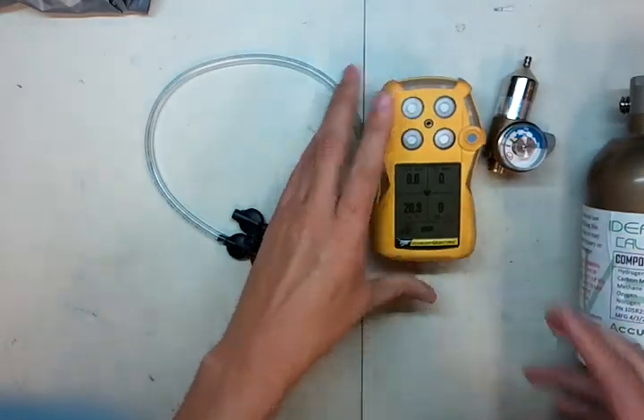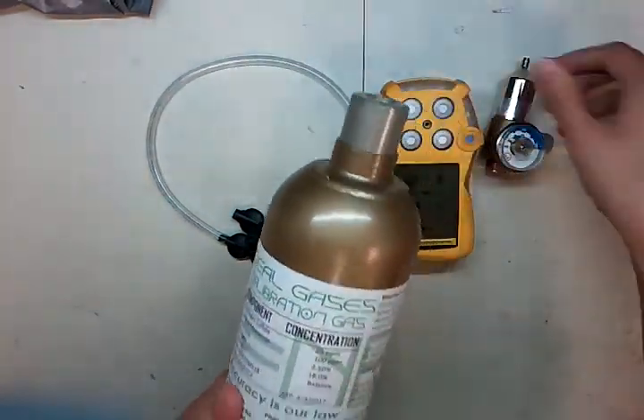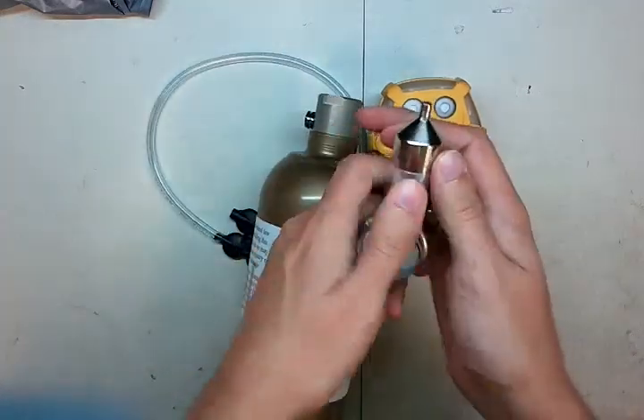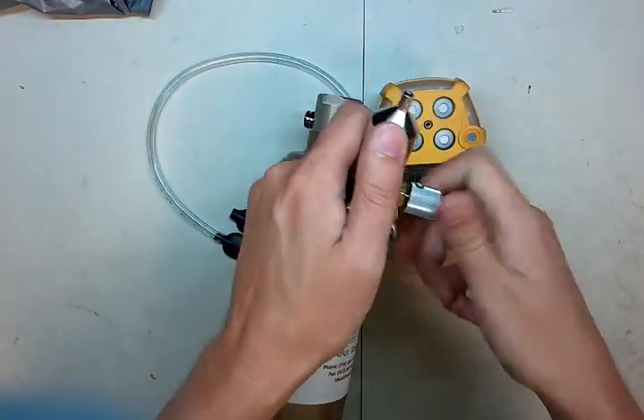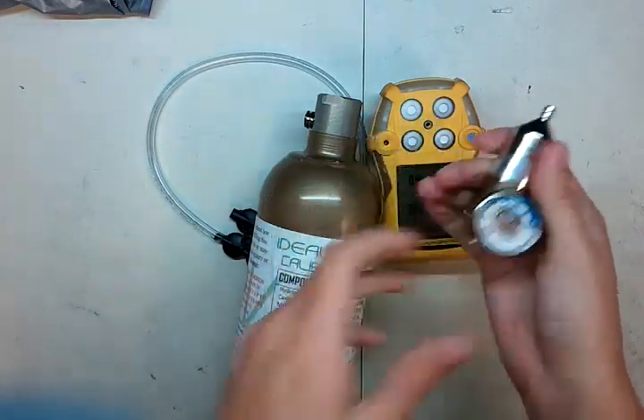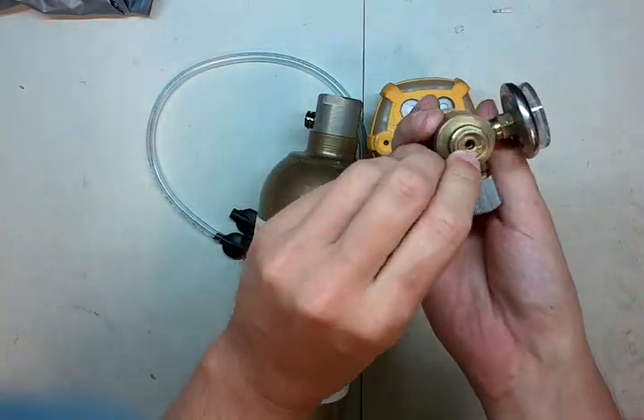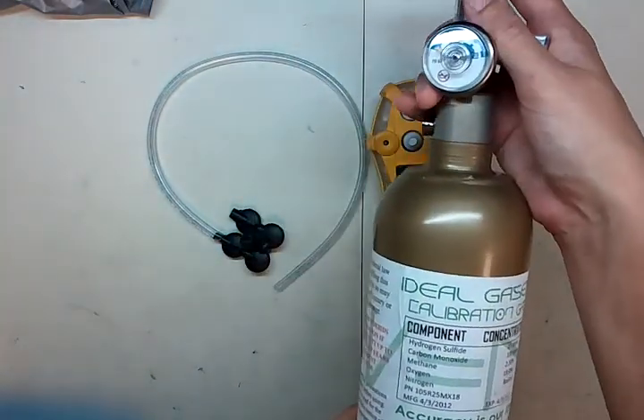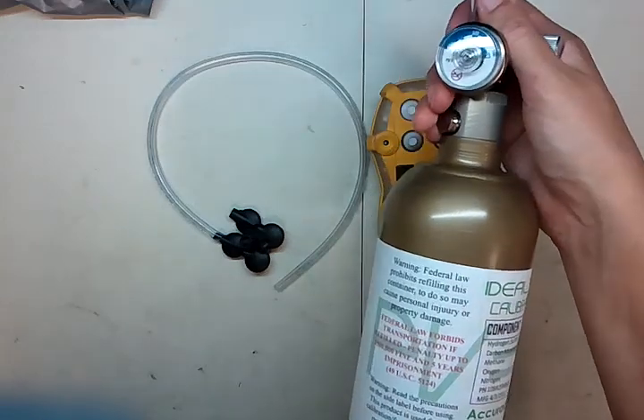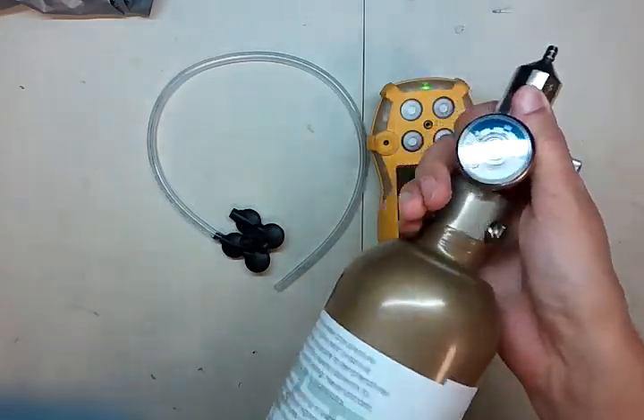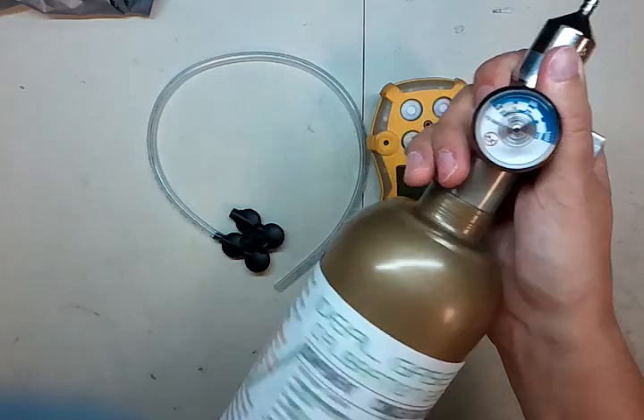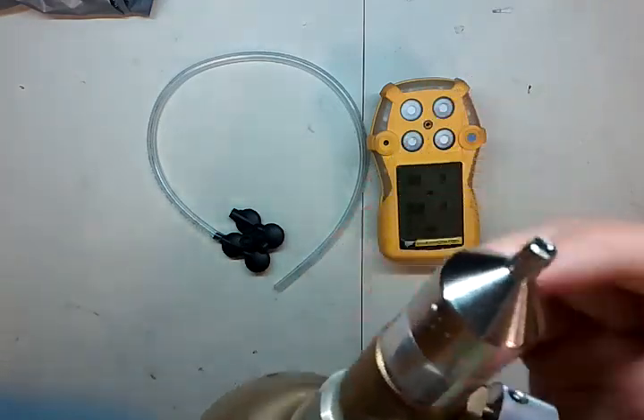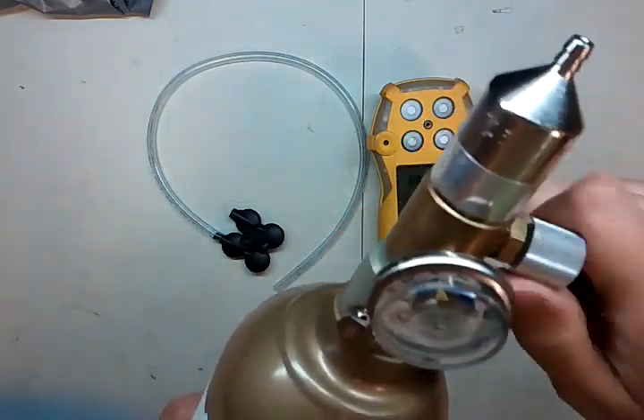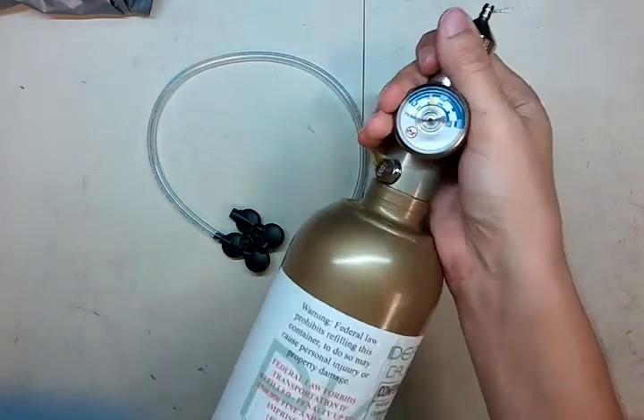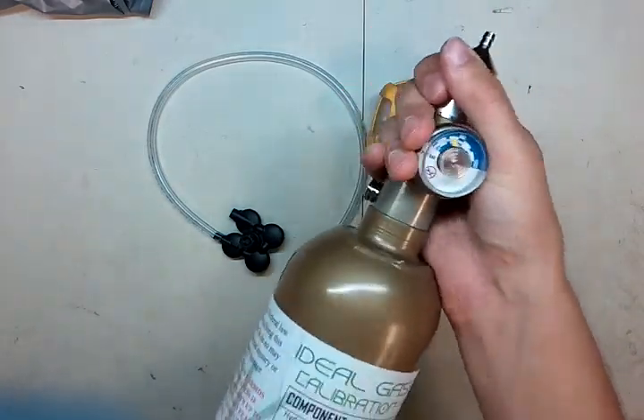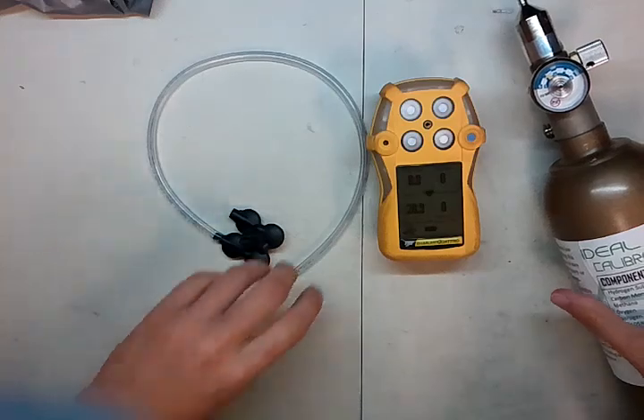Okay, first things to do when we start up, take our calibration gas, take our regulator, and first step, open the regulator. You want to make sure you open that regulator, otherwise you're going to take gas that's up inside here and you would end up jamming it inside there, and the pressure will kind of mix it in. You don't want to get room air mixed with your gas because it has a tendency to fade the hydrogen sulfide out. So once you hear it going, go ahead and turn it off and continue closing it. Put that off to the side here.